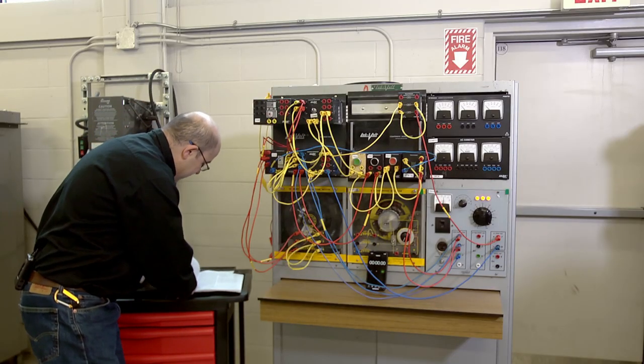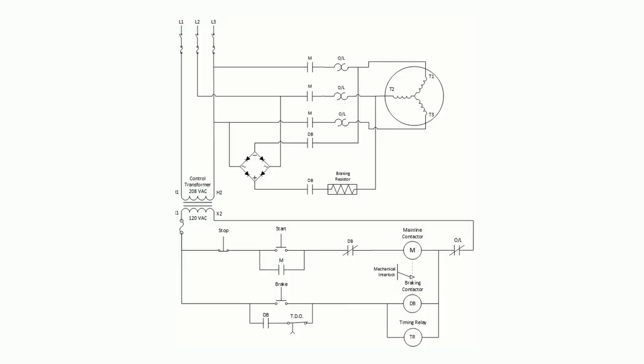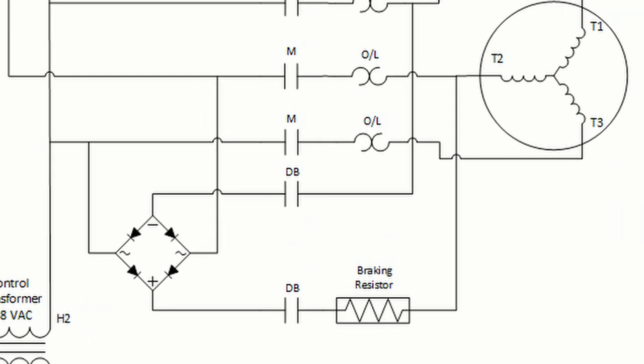Now this is an example of the circuit on page 25-2 where you can plainly see we're going to run DC current through and bring it to a quick stop. This requires two contactors. One would be used in its normal procedure with a push button, and we have a second contactor because we've got to isolate the power supply and run DC current, so we have an electrical interlock also.